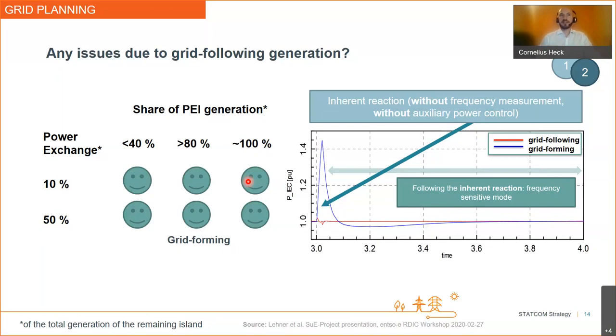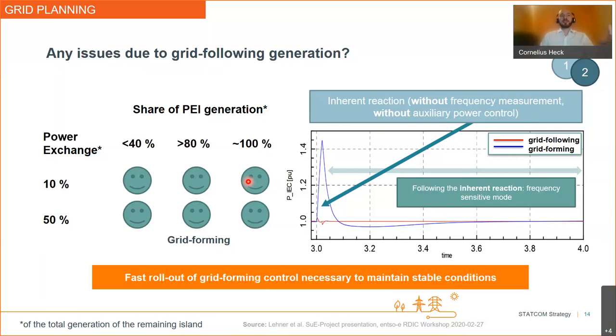We don't need to have everything as grid forming. Some might still be okay to be grid following. And we will always have some synchronous machines in the grid coming from pumped storage units, from underlying combined heat and power plants, and so on. But it really shows that we need to start rolling out grid forming control as fast as possible to not come into this problem where we have the two frowny faces already at a 40% share of renewable energy generation.